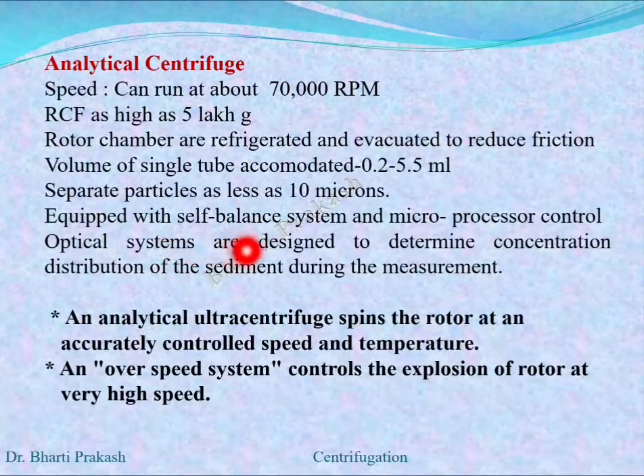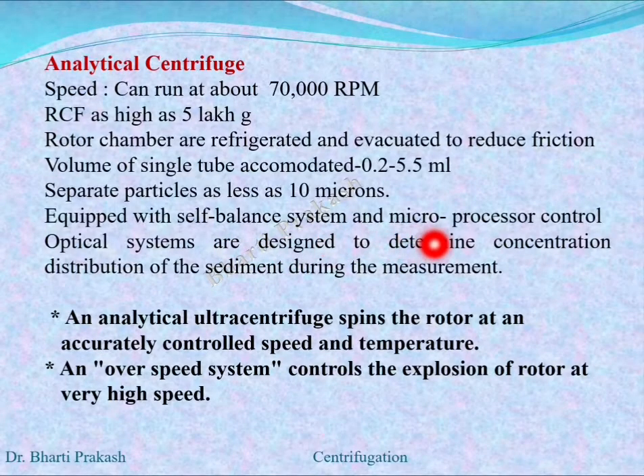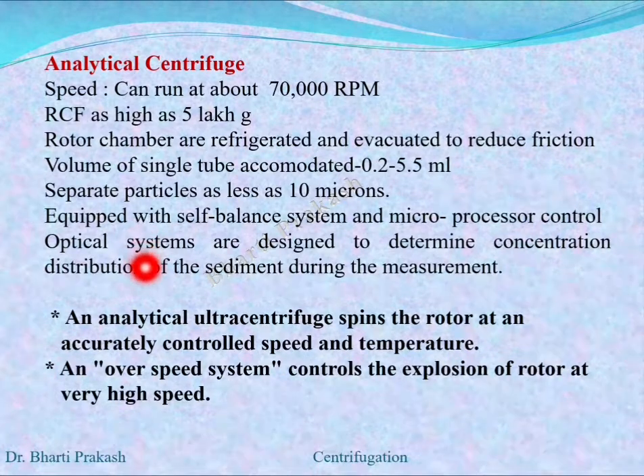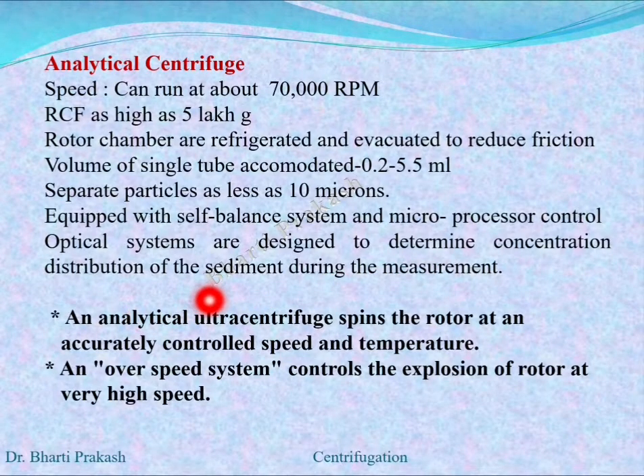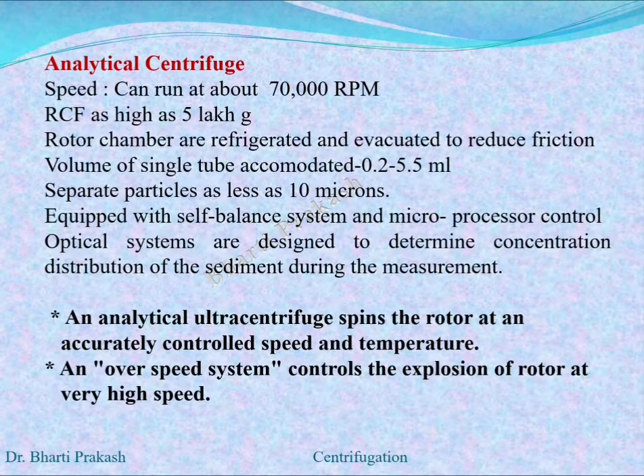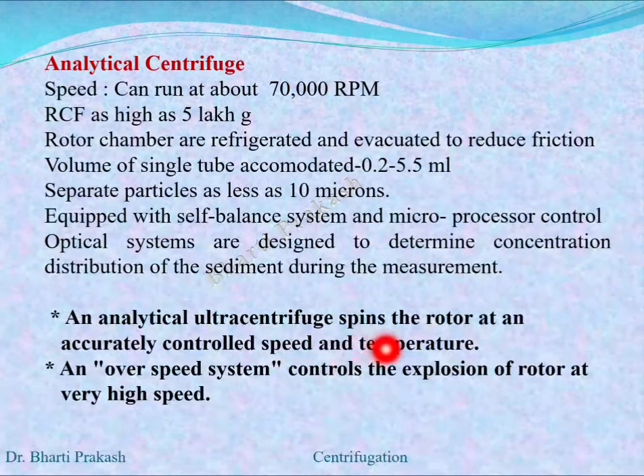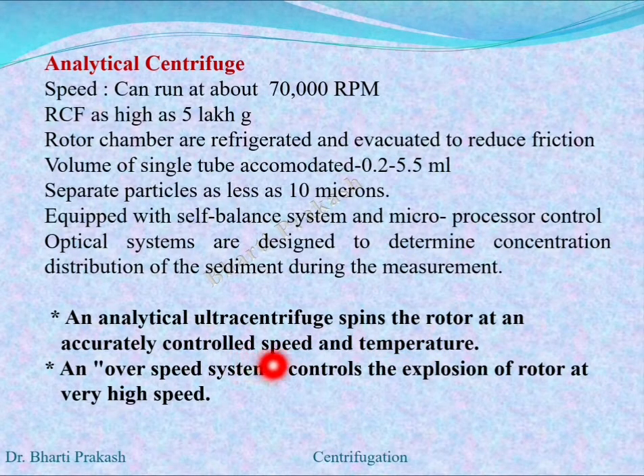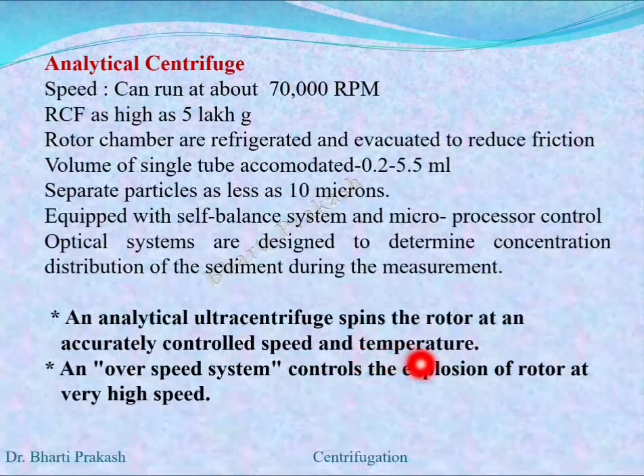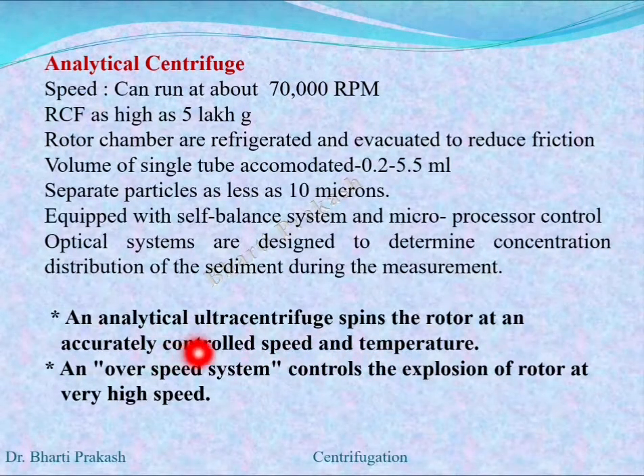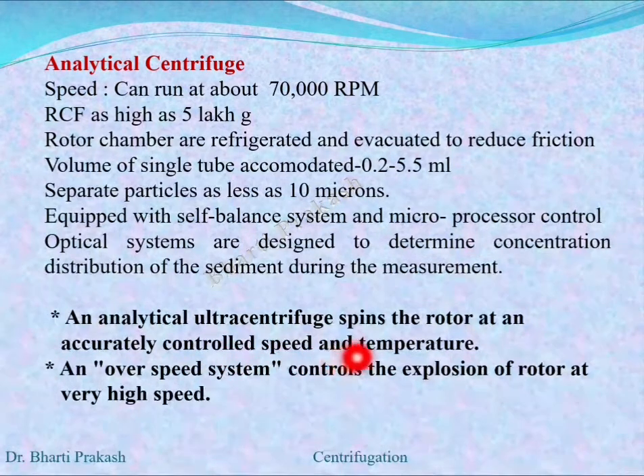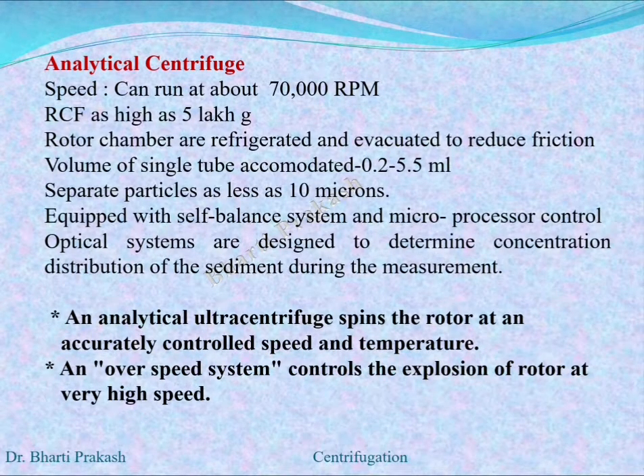These are equipped with a self-balance system and microprocessor control. The optical systems in the analytical centrifuge are designed to determine the concentration distribution of the sediment during measurement. The analytical ultracentrifuge spins the rotor at an accurately controlled speed and temperature. It also has an over-speed system which controls the explosion of the rotor at very high speed.